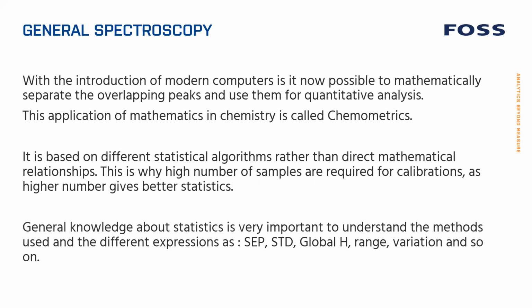In a simple case, where you have one peak absorbing from a change in the molecules, you can just plot the peak height or the peak area against the concentration and get a nice calibration out of that. Here you need to use statistics instead. You use statistical algorithms to make an indirect mathematical relationship with your spectra. This is why we need such a high number of samples for doing calibrations. More samples give better statistics.